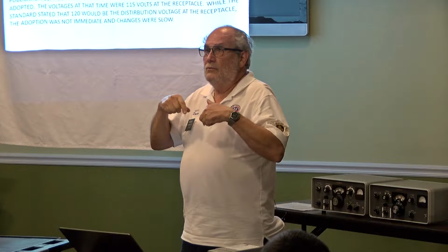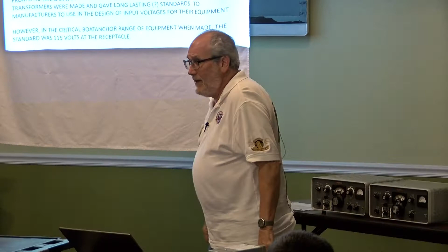The standard is now called ANSI C84.1, adopted operating ranges for the distribution systems in an attempt to address the increasing use of electrical energy. Higher distribution voltages and step-down transformers came to be a normal design mode for large loads. In '54 and again in '75, new voltage ratings, primarily for motors, appeared, and a range of voltages allowed for the distribution system was given. This was the first time that a range of voltages was given. This was designed to end the tendency for a slow increase of voltages in the distribution system. And to that effect, it worked.